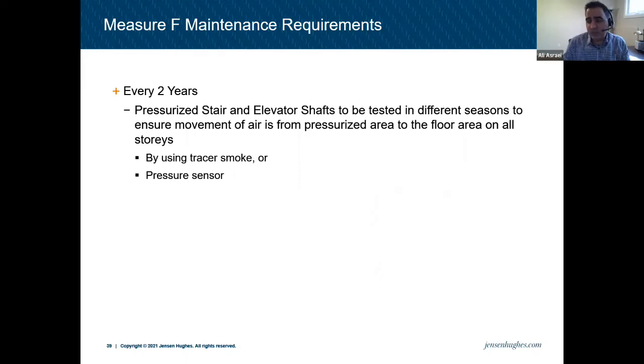The National Fire Code is asking for pressurized stairs and elevator shafts to be tested in different seasons to ensure movement of air is from the pressurized area to the floor area. So basically, every 2 years, you can do it in the summer and in the winter season. Just make sure in both seasons, because the stack effect and the temperature outside affect a lot of these systems in the building, which again should have been considered at the time of the design, because there is a sentence in the OBC and there's a supplementary standard for the temperatures and whatnot they have to follow. But we have to make sure that this works in both seasons.